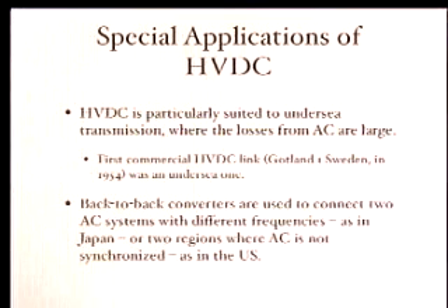The other thing about high-voltage direct current transmission is it's particularly suited to certain specialized applications. In particular, it's very suited to undersea transmission, where the losses from AC are larger. Another important use of direct current is back-to-back converters, where you want to connect two AC systems operating at different frequencies. In Japan, half the country runs on 50 hertz and half on 60 hertz, so the only way of transmitting power between the two halves is to convert to and from DC.